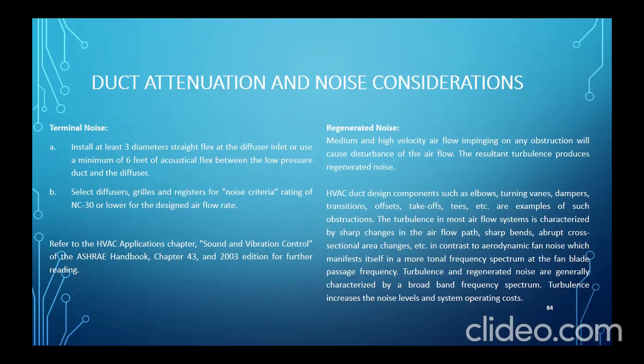The turbulence in most airflow systems is characterized by sharp changes in the airflow path, sharp bends, abrupt cross-sectional area changes, etc. In contrast to aerodynamic fan noise, which manifests itself in a more tonal frequency spectrum at the fan blade pass frequency, turbulence and regenerated noise are generally characterized by a broadband frequency spectrum. So turbulence increases the noise level and system operating costs.